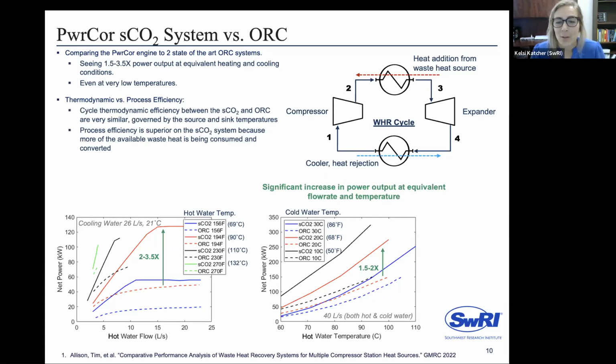What it comes down to, as mentioned earlier, is the difference between thermodynamic efficiency and process efficiency. Thermodynamic efficiency is about how much of the heat coming into your primary heater gets converted into usable mechanical or electrical power at your expander. Comparing an SCO2 cycle to an ORC, the thermodynamic efficiency is pretty similar - SCO2 is maybe 5% improved. But the key improvement is in process efficiency: because we're able to take more heat out of that process stream and convert it into usable power, our process efficiency is much higher, recovering more heat from the waste heat stream or geothermal fluid coming out of the well.